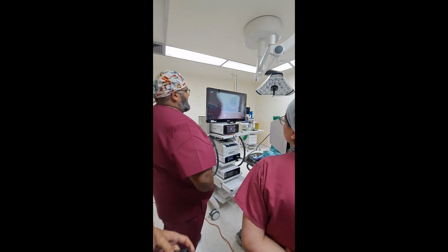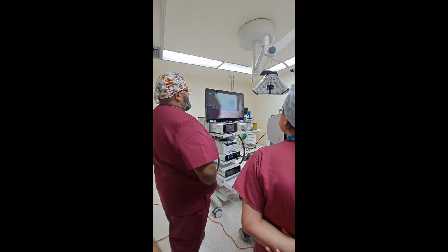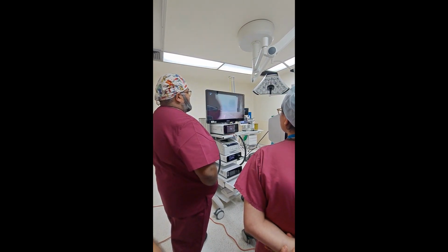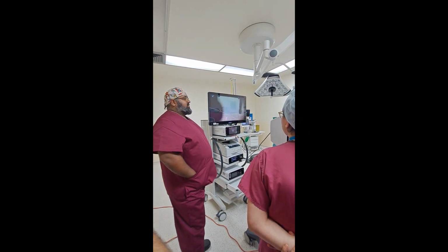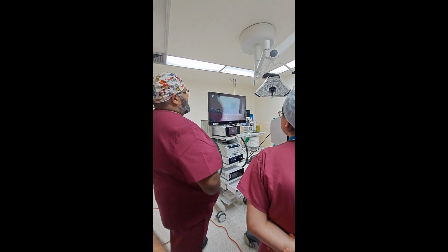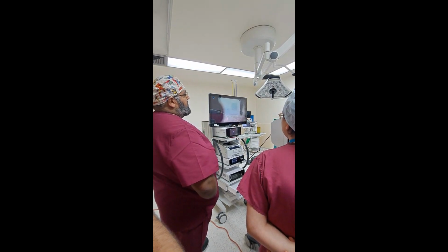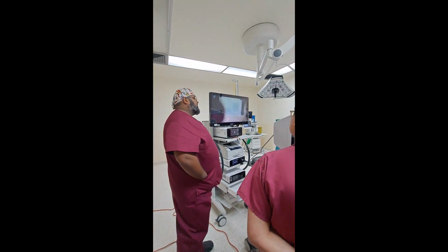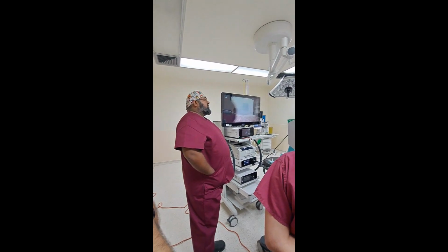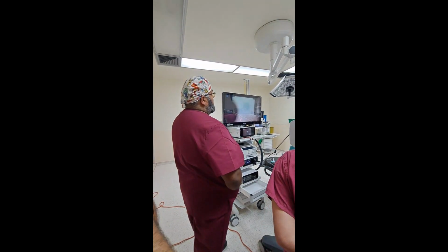With the micro manipulator, when we're setting this up, we need to parafocalize the micro manipulator with the focal length that we're working at with the microscope. So we spoke about 400 millimeters here, and this has a couple of rotation rings on it, so we're parafocalizing it. The micromanipulator and the laser are working at the same working distance as the microscope. So that's around 400, and that will give us the crispest beam.